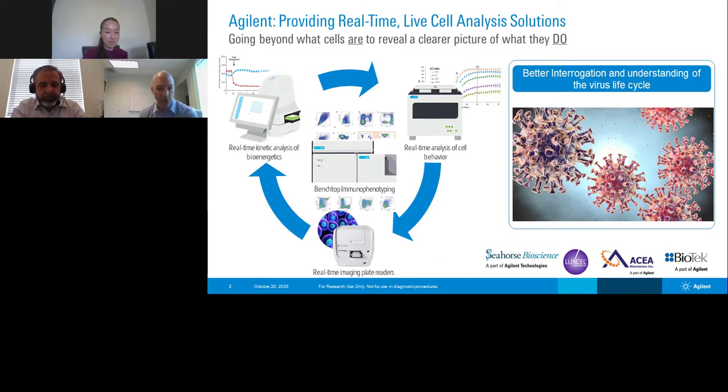One for Xiaoyu. Are the contractility and electrophysiology measured from individual cells? Thank you, Brandon. When you use the CardioECR system, we have two sets of different electrodes, as I mentioned during my talk: impedance electrodes and field potential electrodes. The impedance electrodes measure the average signal from the entire cell monolayer, so not individual cells.